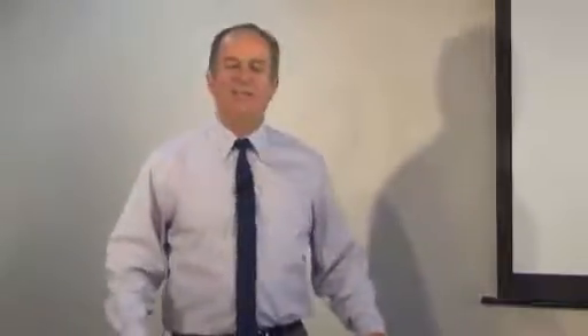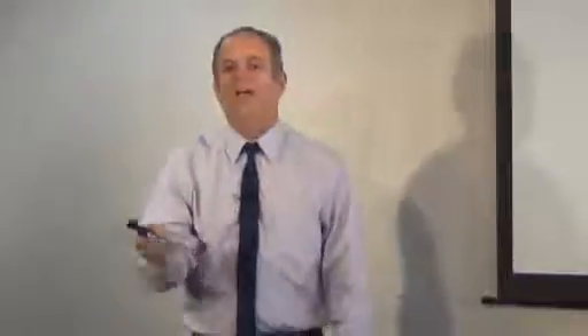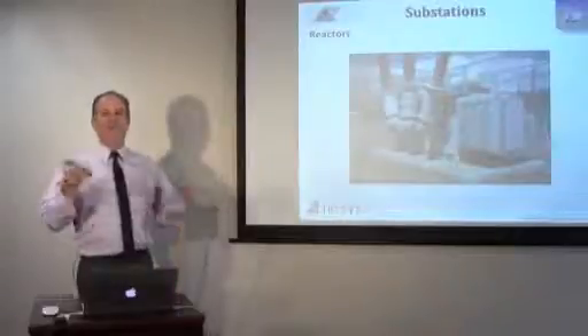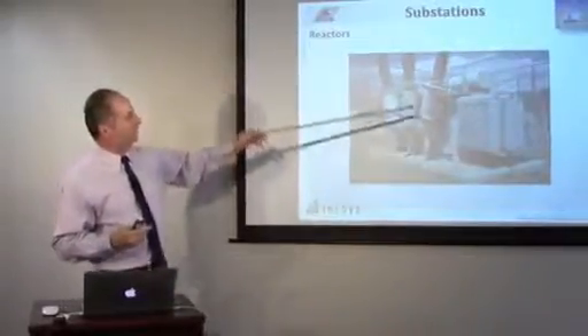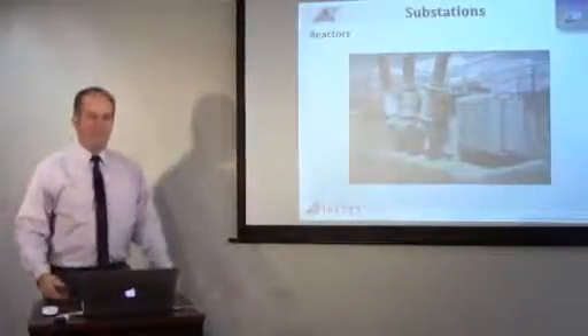It acts as an AC load. If there is a very long transmission line, the purpose of this particular one, a 200-mile 345 kV transmission line, when you energize that line at one end, the other end, because of the capacitive effects of a very long transmission line, the charging and the static charge and what have you, you actually end up with maybe 365, 375 kV instead of 345. So you have the reactor on when you energize that line. You're going to learn this if you're doing system control operator stuff. This is what the reactors are for. So when you energize that line with the reactors on, now you're at maybe 355. Then you can close the circuit breaker to the transformer, pick up load, and let the load hold the voltage down and turn off the reactor. Okay, so the reactors are used to lower the voltage, okay? So here's a 3-phase, 35 megavar shunt reactor, okay?